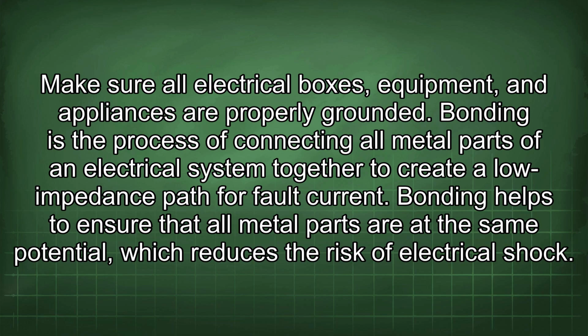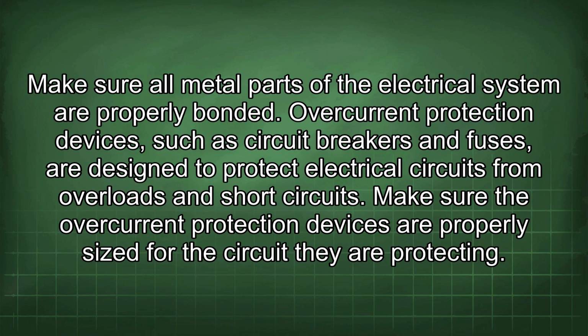Bonding is the process of connecting all metal parts of an electrical system together to create a low impedance path for fault current. Bonding helps to ensure that all metal parts are at the same potential, which reduces the risk of electrical shock. Make sure all metal parts of the electrical system are properly bonded.